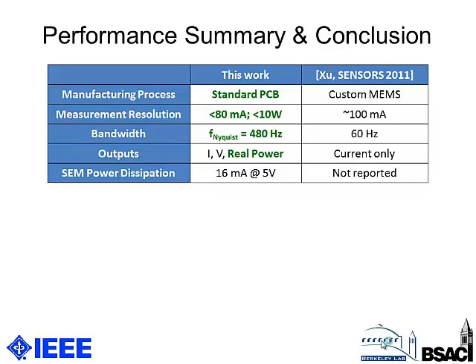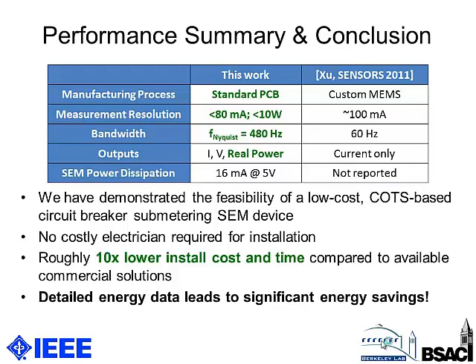In summary, we have demonstrated the feasibility of a low-cost, non-intrusive power metering device built using all off-the-shelf components. Since it's non-intrusive, it can be installed on the face of the circuit breaker panel, so a costly electrician is not required. This leads to roughly 10x lower install cost and time compared to the commercially available solutions outlined at the beginning of the talk. We hope this will lead to more widespread deployment of systems like this, because detailed energy data leads to significant energy savings.